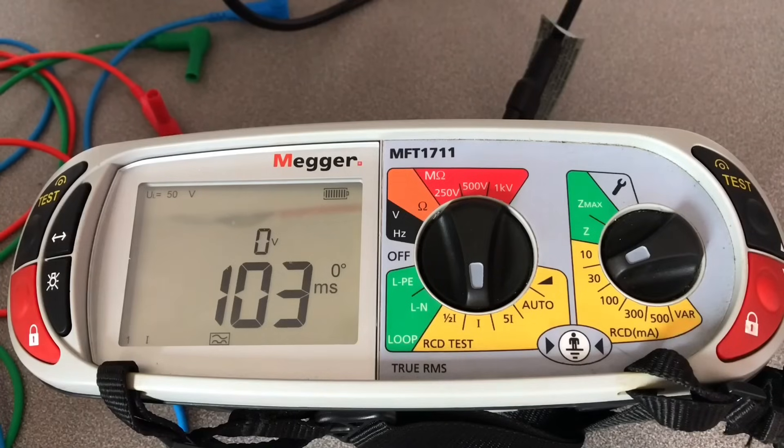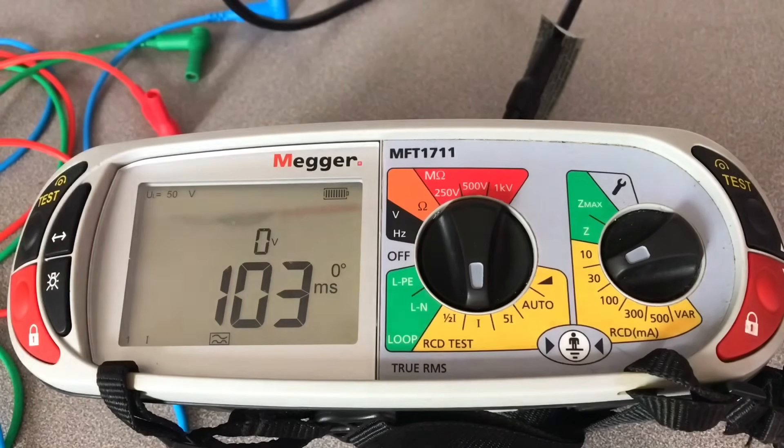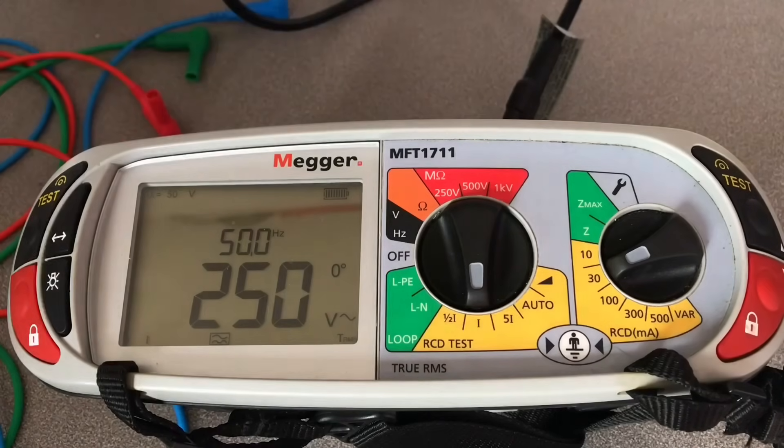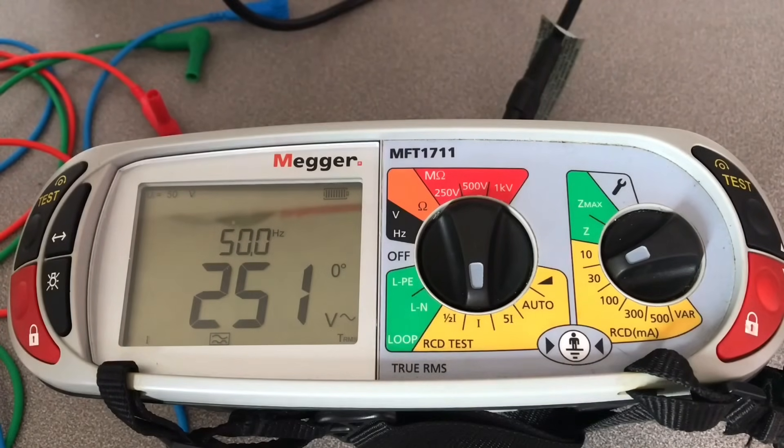Now we're going to test it at one times I-delta-N. We've gone back to zero degrees. We're still on A type. 103 milliseconds. Wow. I've never seen numbers that big before. Still acceptable. However, still on the high side. But it's well within the 300. I think that's probably just going to be a psychological change in thinking that we're not going to see very small numbers. We're now going to see maybe higher numbers than these A type RCDs.